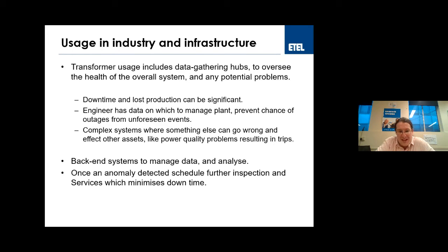Sometimes, in terms of why monitor a transformer, it's because they can be complex systems, and if something goes wrong in the plant, such as power quality problems or a high inrush current, that can cause other assets to trip, like the switchboard.